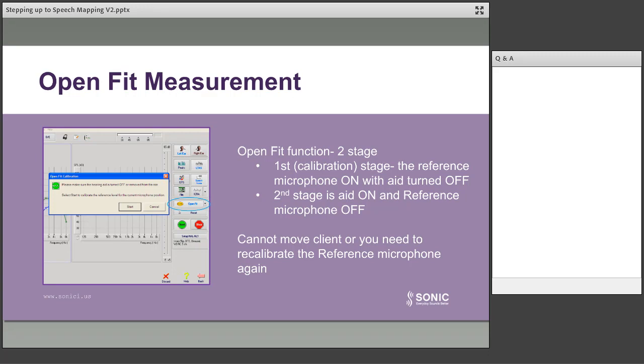Now in the second stage, you turn the hearing aid on and the reference microphone automatically turns off. As the signal's coming and the amplified sound is leaking out of the ear, it no longer interacts with the reference microphone, because you've already set it at a pre-set calibration level. And that works well as long as the client doesn't move. So if the client decides to jiggle around or sit back, then you will need to start that process again.